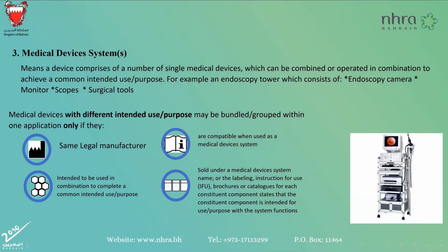The third bundling group is the medical devices system, which is quite straightforward. It means that a number of medical devices that are combined or connected together to achieve a common intended use or purpose can be bundled together in a single application. They should, however, be under the same legal manufacturer and sold under a medical device system name as a single package. Also, the brochure or the catalog or the instruction for use should show or state that each component or device is intended to be used within the system.